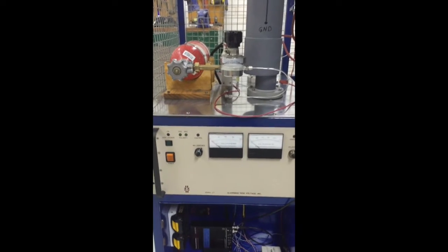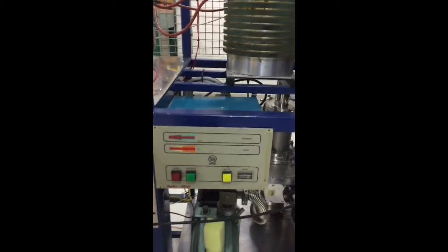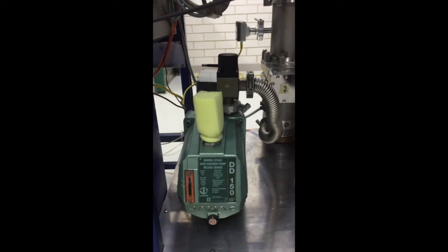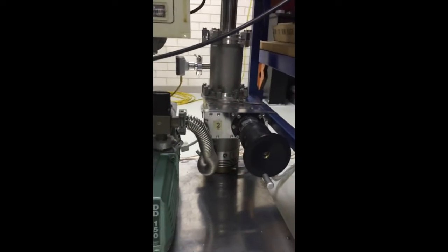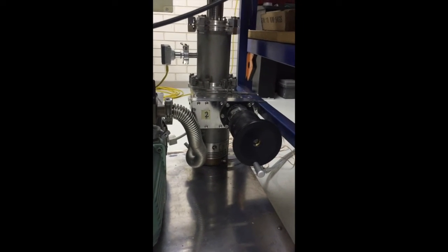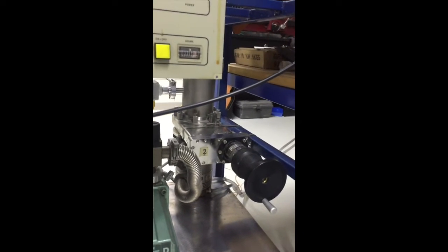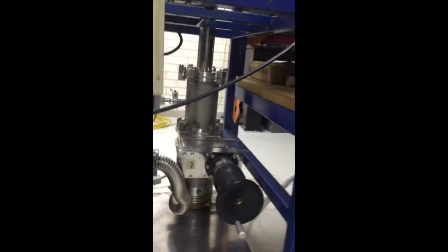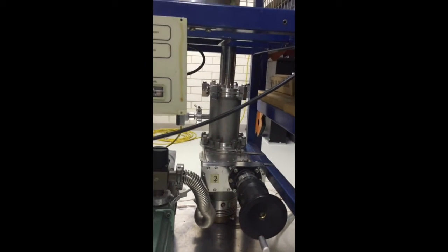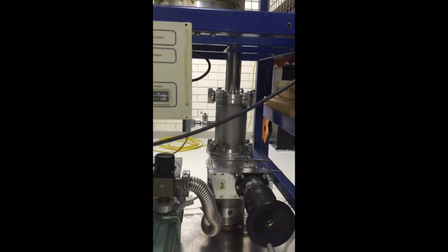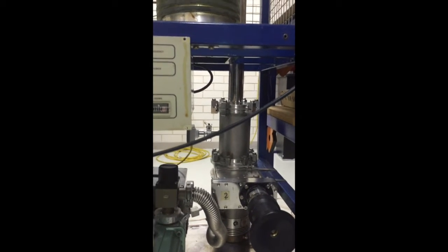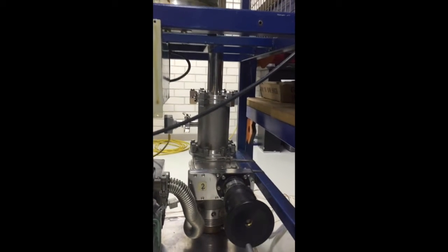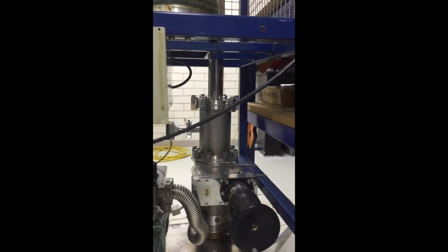That's operated from LabVIEW. I've got the vacuum pump controller. At the bottom here we have a JVac rotary vane pump, and that goes to a Varian turbo pump. And then we have a big gate valve with a manual handle, and that goes into an ISO 100 flange and another ISO 100 flange, which has a welded tube that goes up to the NW25s.